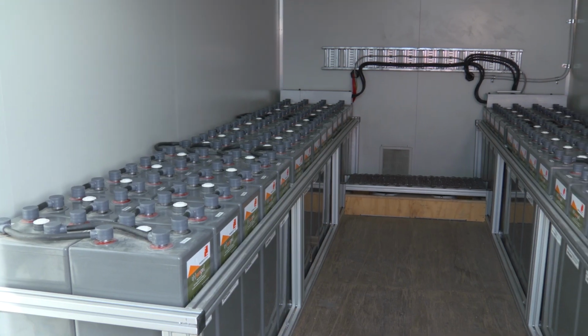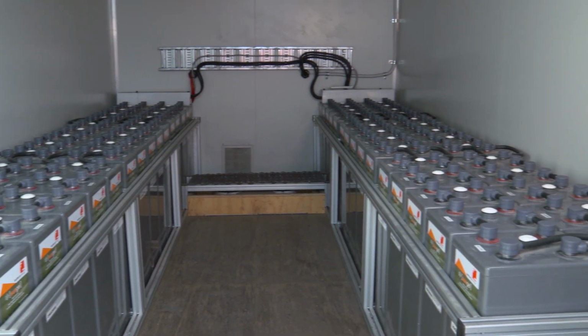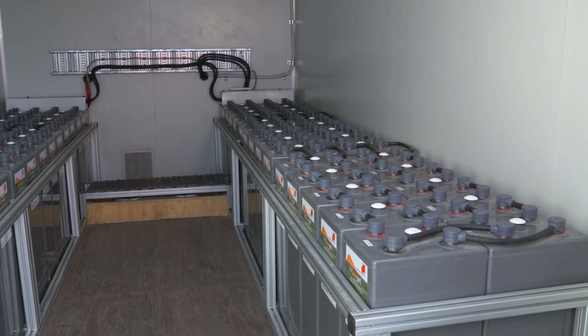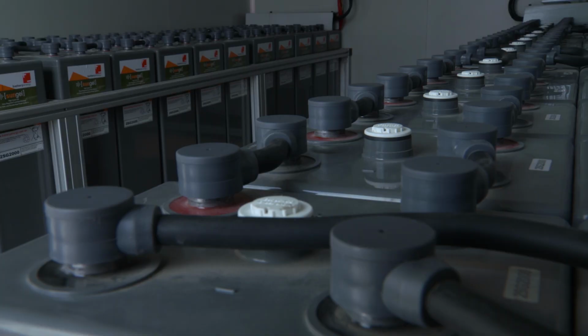But we had an opportunity there where we had a battery, a very large battery set, that we knew would be able to actually blend mains with battery power. And through a fair bit of engineering, we loaded the system here at site and we tuned it and tuned it and tuned it. And now what happens is anything above that 80 amp per phase load for the brewery, we supply out of batteries.